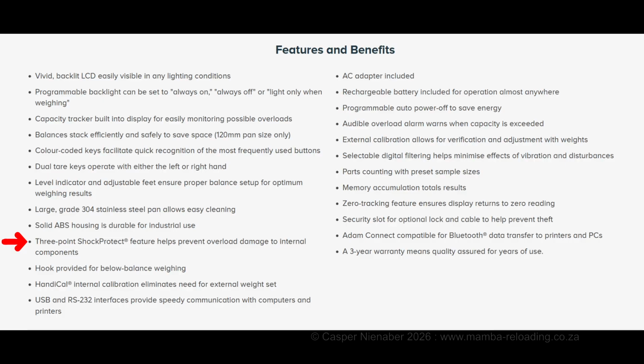The 3-point shock protect feature helps prevent overload damage to internal components, something I'll later prove by massively overloading the balance. A hook is provided for below balance weighing. The HandiCal internal calibration eliminates the need for an external test weight set, which I'll demonstrate shortly. The USB and RS-232 interfaces provide speedy communication with computers and printers. An AC adapter is included.